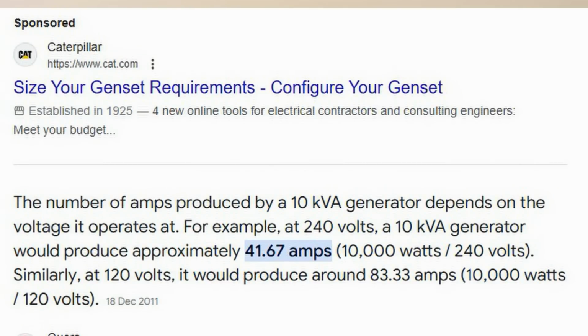If you don't believe me, or you're not convinced, I'm putting an image on your screen right from Google. You can just put it in yourself: what is the full load amps of a 10 kVA generator? On this screen, they've used 240 volts and got about 41 point something amps. The Ghana system is 220 volts, so when you do that, you get a higher number, around 45 amps.